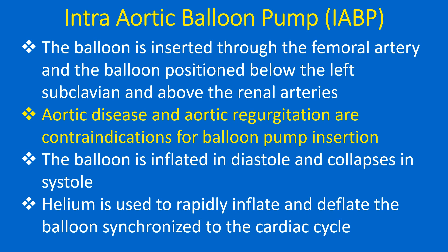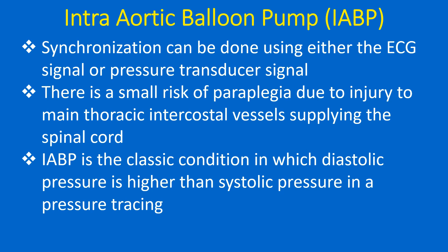The balloon is inflated in diastole and collapses in systole. Helium is used to rapidly inflate and deflate the balloon synchronized to the cardiac cycle. Synchronization can be done using either the ECG signal or pressure transducer signal. There is a small risk of paraplegia due to injury to main thoracic intercostal vessels supplying the spinal cord. IABP is the classic condition in which diastolic pressure is higher than the systolic pressure in a pressure tracing.